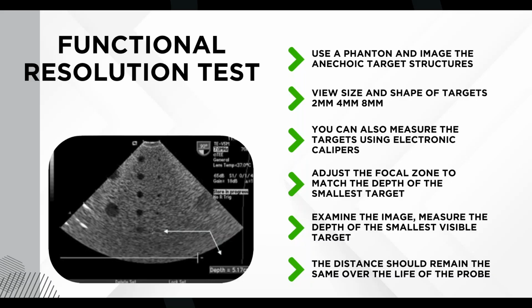Again, same type of thing. For functional resolution, before we were just going to the depth of penetration just to see how deep the transducer goes. This is actual functional resolution or usable resolution. You can call it either way, but this would be the resolution that they could actually use to see images on particular here. So you can see it. This is carotid. And the functional portion of it, I wouldn't be able to see anything deeper than that would be usable below that 4 centimeter mark. All right, again, record it.